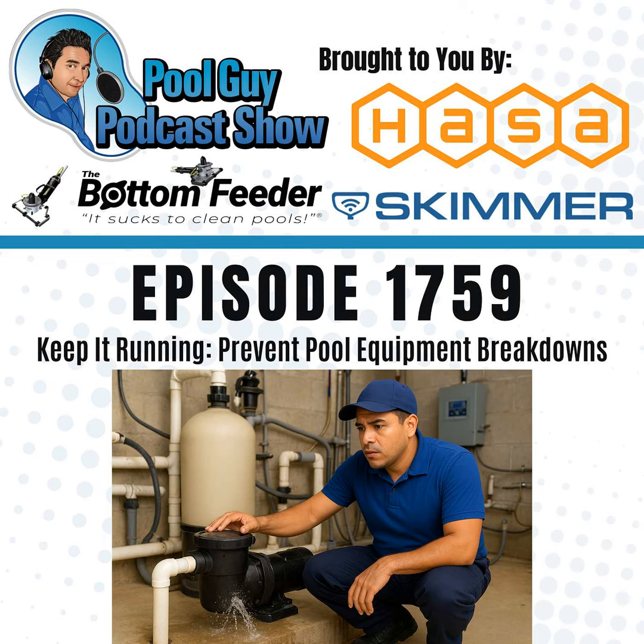And then, of course, other things are just cracks and age with the filter. But I wanted to give you some realistic problems you're having with filters, and this is what you're going to run into mainly out there. As the filter gets older, the clamp will start to fail because the threaded part starts to get stripped, and you'll have other leaks and things like that appear.